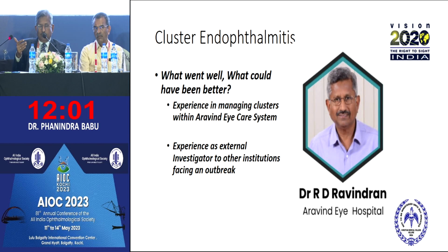That's what I understood. From the investigations, we found that that particular theater's bin was autoclaved last. And from whatever I could understand later from the postmortem, there had probably been a compromise by the CSSD staff in completing the whole cycle. So it becomes important to use a set of different indicators, not just class 1 indicators. Once we moved on to class 5 indicators, we were able to pick up even cycles that went through a regular full cycle but were still deficient.